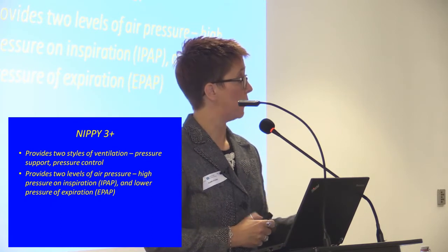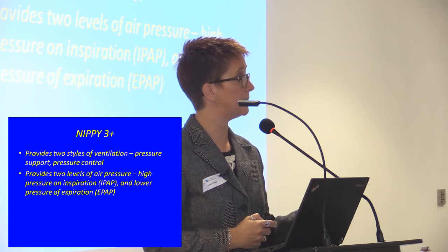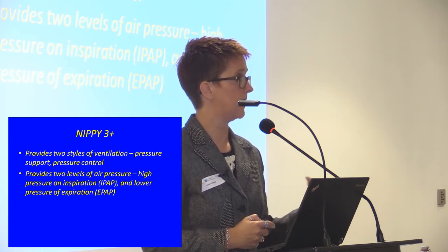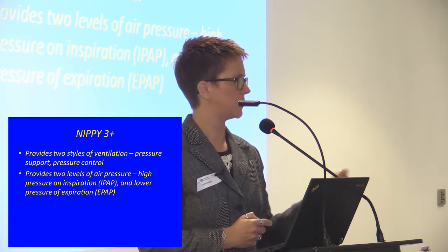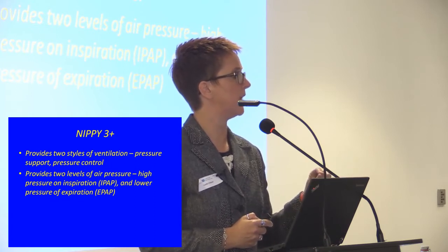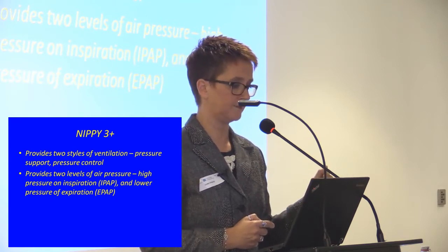There are 2 styles on the NIPPY 3+ that we deal with. First style is pressure support. Clues in the title, it supports the person's effort. So when they demand a breath, they get a breath from the machine. Pressure control, again, is like pressure support, but it has a timed element in it, so we can lengthen the period of time that they get the breath in, which may allow for more time to flush out the carbon dioxide.